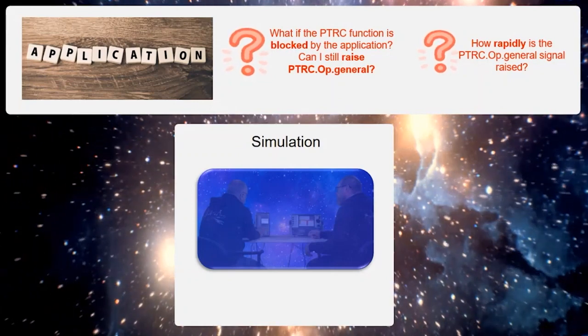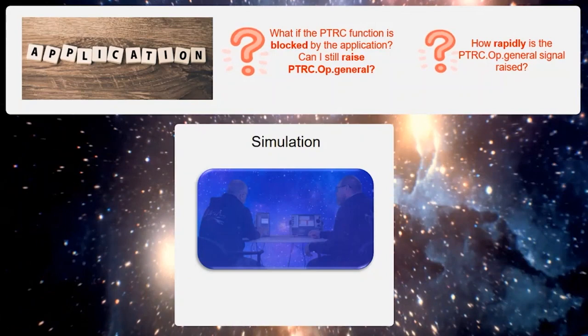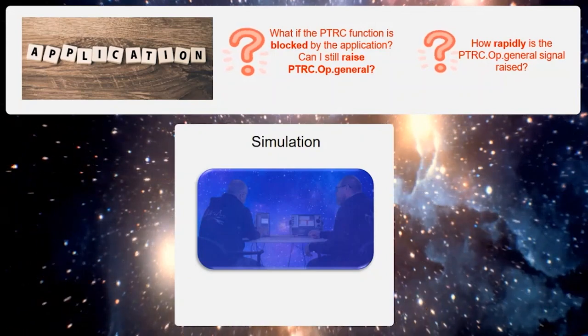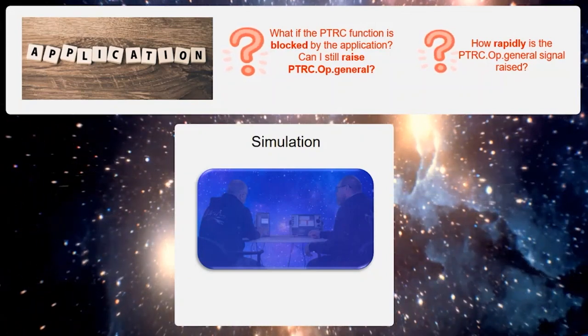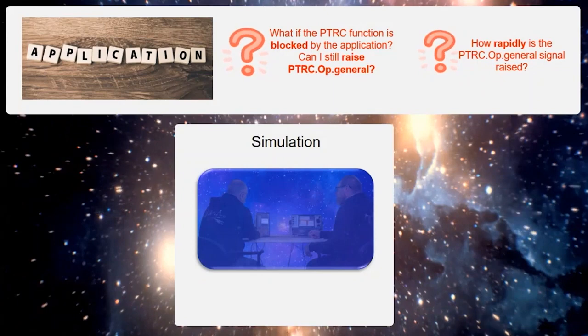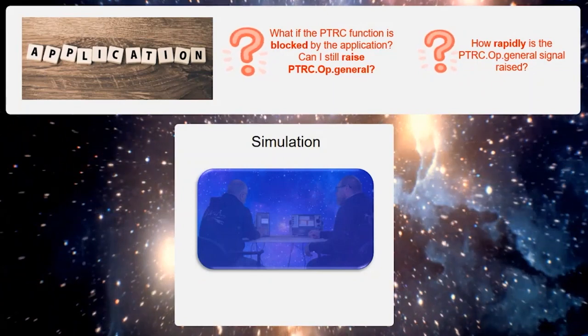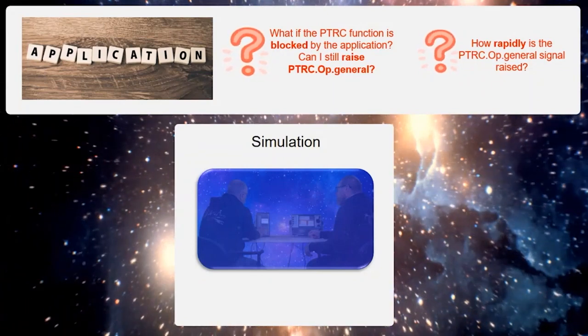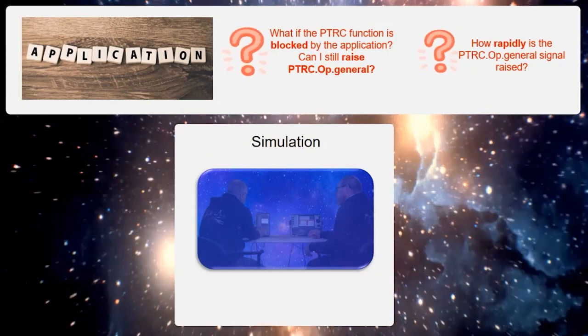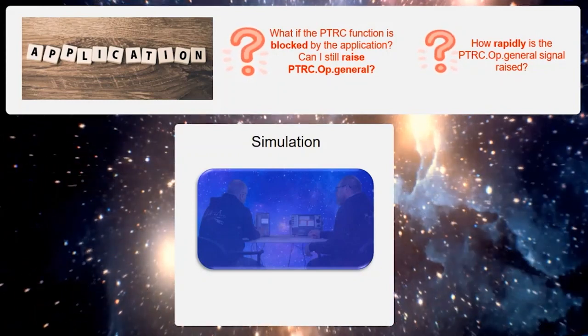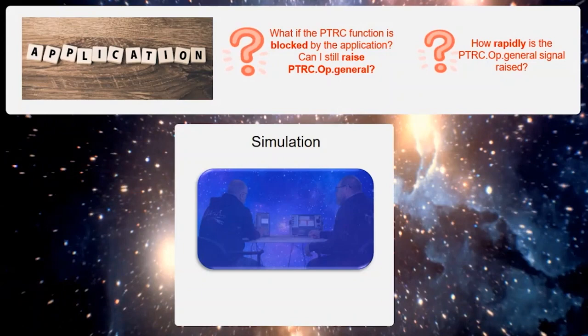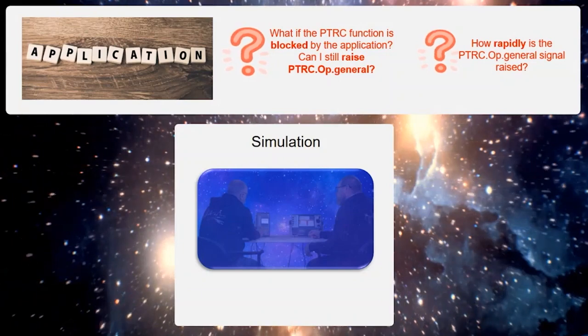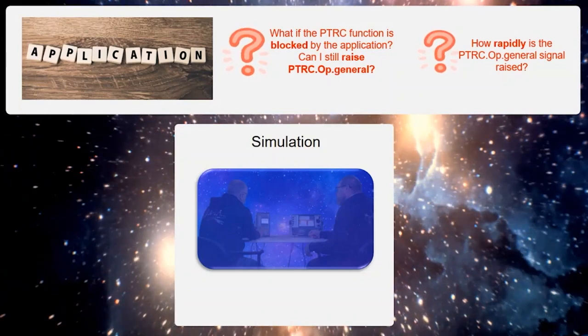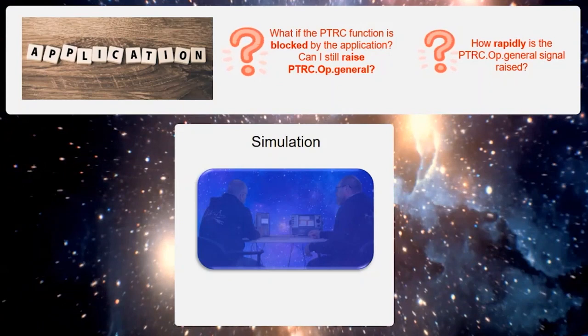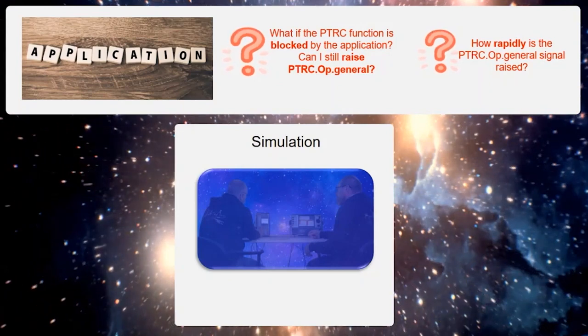I really cannot send the message. I cannot raise the general trip at all, but the SCL file allows me to raise it when I simulate the SCL file, because the general trip, the protection function, is blocked. It's blocked by a binary input. So it cannot trip if it is blocked, but when I simulate the SCL model, I can simulate the trip without considering the application.